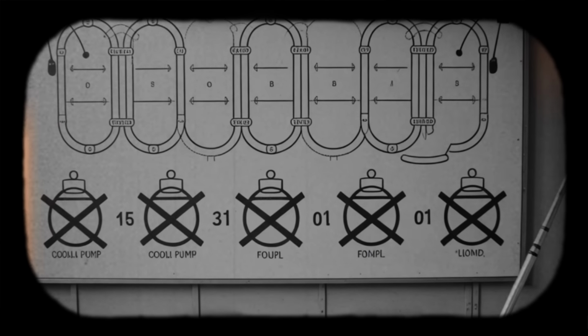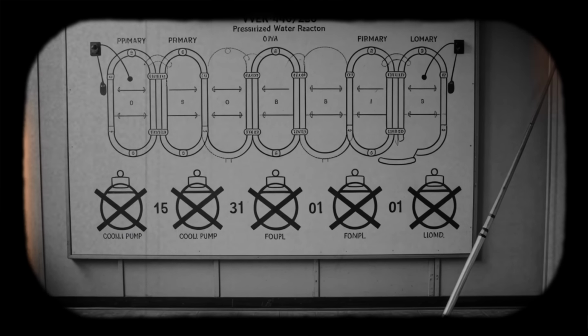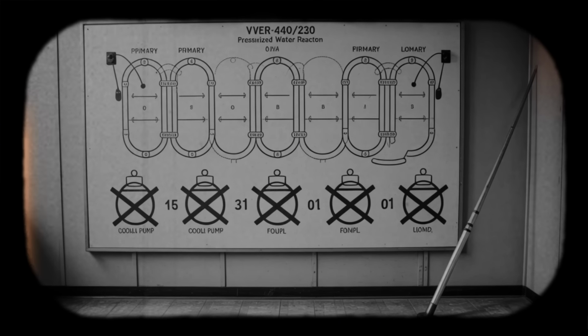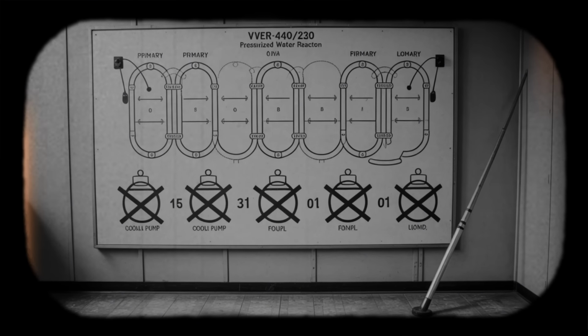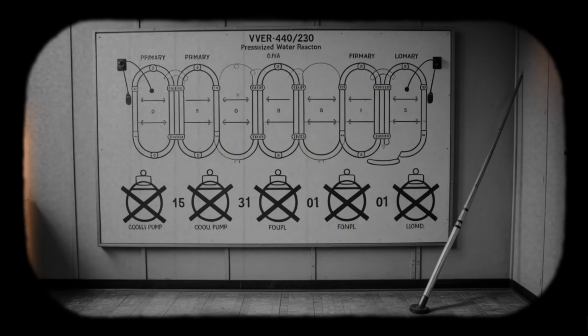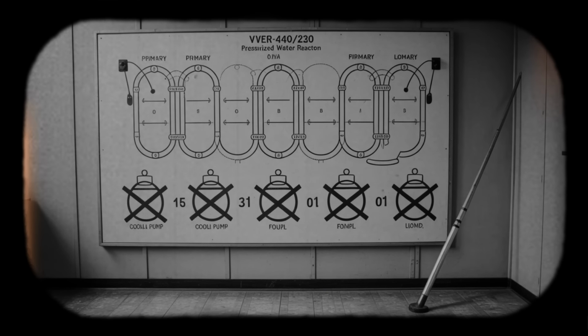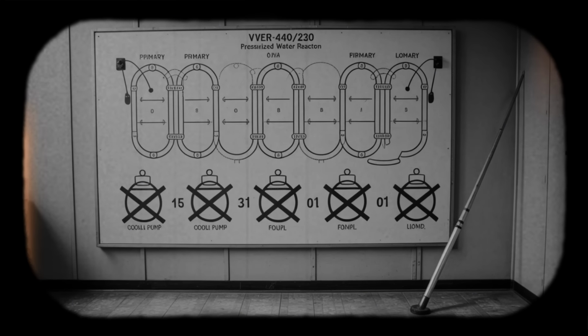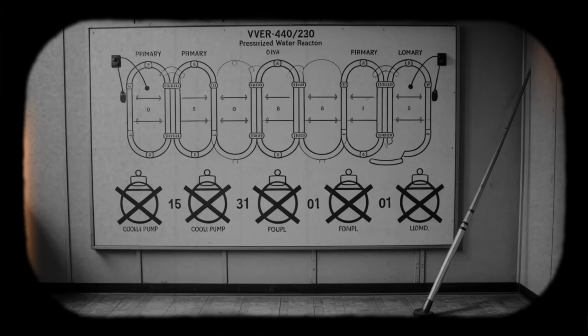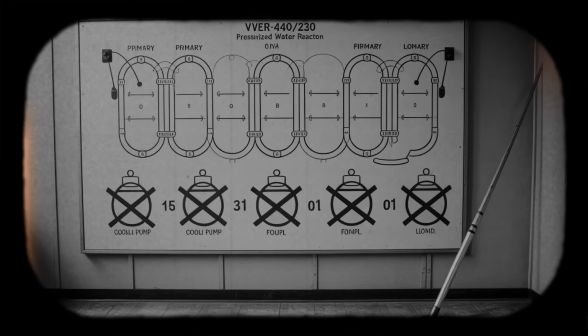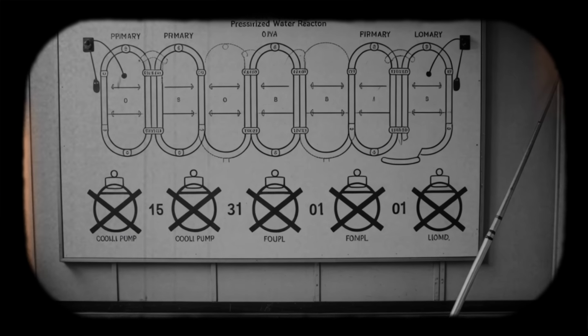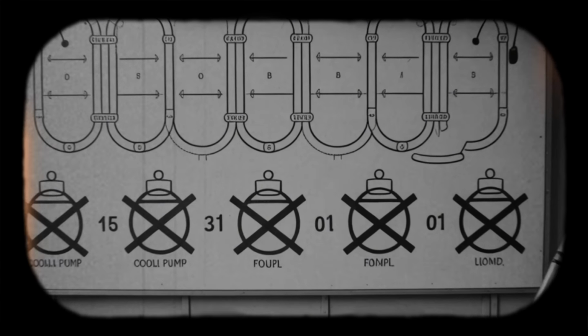US NRC fire incident analyses documented what happened. Secondary cooling was restored by routing a spare power cable from an alternate source, apparently from Unit 2, directly to one auxiliary feedwater pump. This cross-connection was not part of original emergency operating procedures. Design analyses had treated each VVER 440 unit as largely self-contained for safety purposes, minimizing inter-unit dependencies. But the fire scenario had invalidated those assumptions. Unit 1's internal emergency power was insufficient. Its cable routing had betrayed redundancy. An external power source became the lifeline.